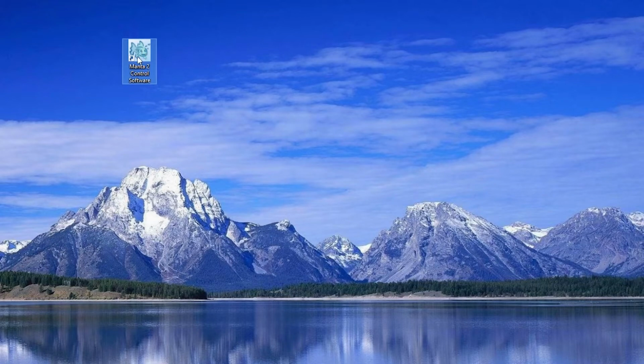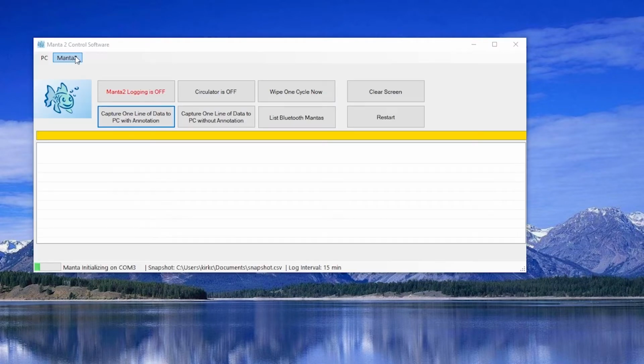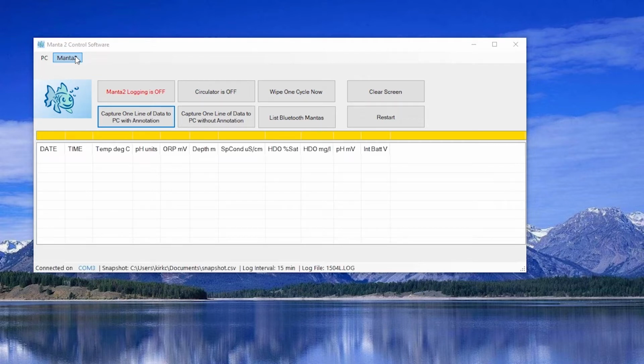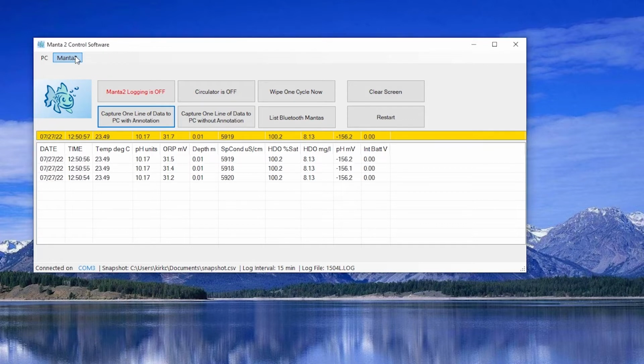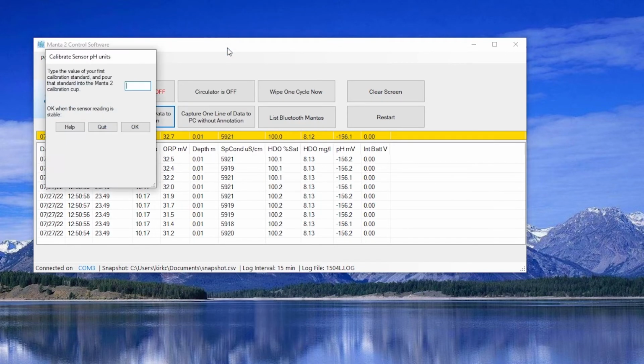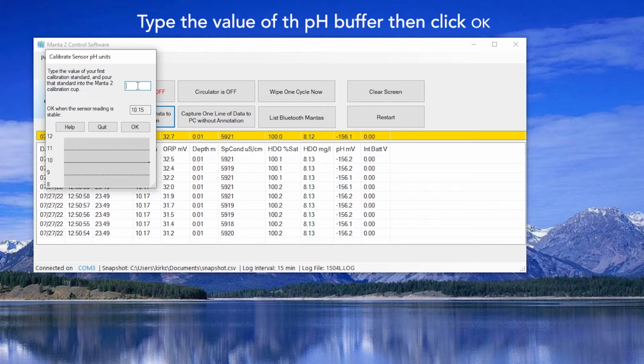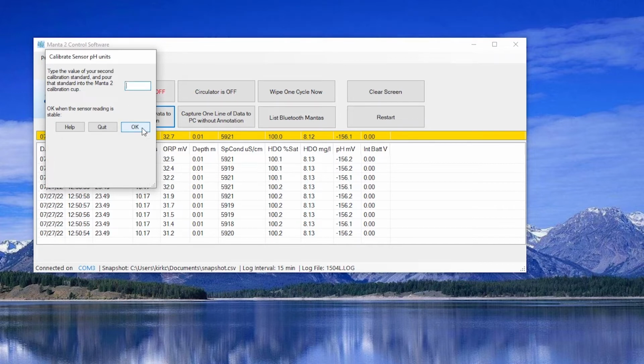Start your program as usual by clicking the icon on your desktop screen. When your pH reading has stabilized, click on the Manta 2 pull-down menu at the top left-hand corner of your screen, hover over Calibrate, and then click on pH units. You can click OK because you know that your pH buffer's reading has stabilized. You will then be prompted to do your second calibration.